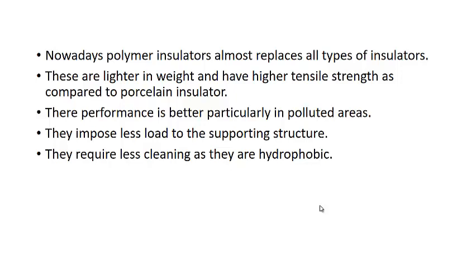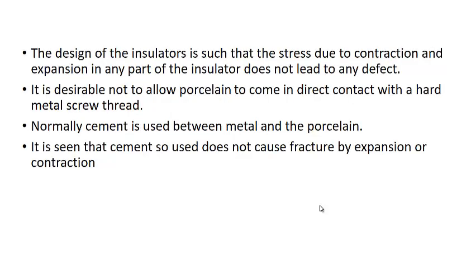Nowadays, polymer insulators almost replace all types of insulators because they are lighter in weight. They have higher tensile strength as compared to the porcelain insulator. Their transportation is very simple. Their performance is better in polluted areas. Since they are very light in weight, they impose very little load on the supporting structure. One more thing, they are hydrophobic. They require less cleaning action. So this is about the polymer insulators.